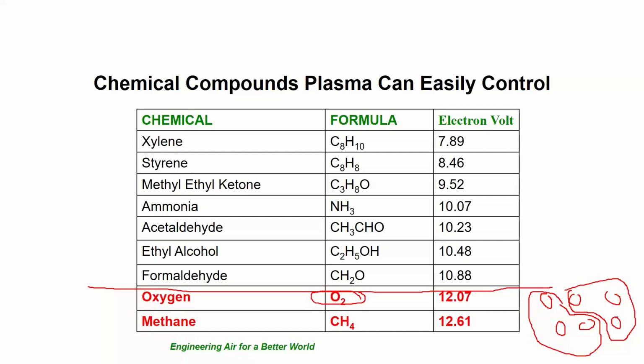So anything above 12 electron volts, it can't break down. So there's no ozone production with ionizers, zero. That's another reason they've become more popular, because people are trying to get non-ozone things, which is the new recommendation from Ashrae. So that's what they want. Stuff less than 12 electron volts, we can break down.